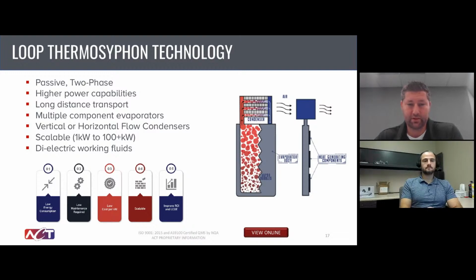So same design principles or considerations here. You're evaporating at your heat source and you're condensing at your heat sink. But because you're running in a full loop and it's designed strategically so that when you're condensing, you're continuing the path of the loop, you never have the forces interacting. So your vapor is flowing one direction, your liquid's flowing continuously along the loop. In a heat pipe or a typical thermosyphon, those forces would interact. So your vapor would be flowing down the center and your liquid would be returning around the outside, but that creates some inertial forces within it, which limits your overall capacity. So in the case of a loop thermosyphon, you can move more heat in a similar form factor.